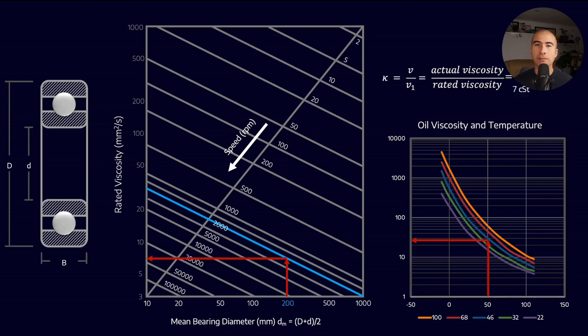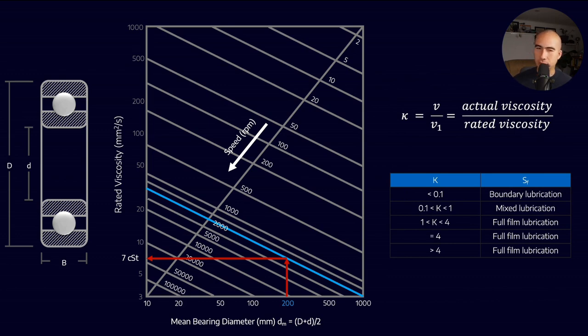With kappa ratio, 0.1 and lower indicates boundary lubrication with basically no lubricant film. Between that and about one is mixed lubrication, where actual versus rated viscosity is on the same order of magnitude. Beyond that is full film lubrication. A higher kappa ratio extends bearing life. Bearing life increases until kappa ratio of four - beyond that, additional film thickness doesn't increase bearing life further. That's why kappa ratio of four maximizes bearing life.